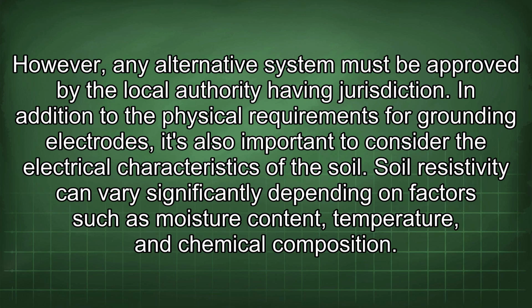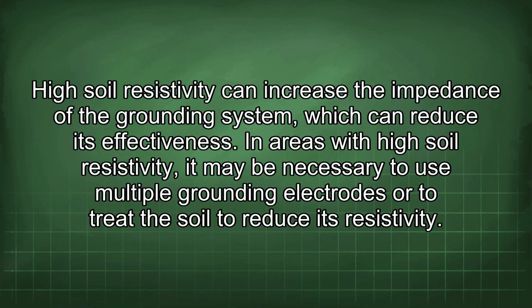In addition to the physical requirements for grounding electrodes, it's also important to consider the electrical characteristics of the soil. Soil resistivity can vary significantly depending on factors such as moisture content, temperature, and chemical composition. High soil resistivity can increase the impedance of the grounding system, which can reduce its effectiveness.